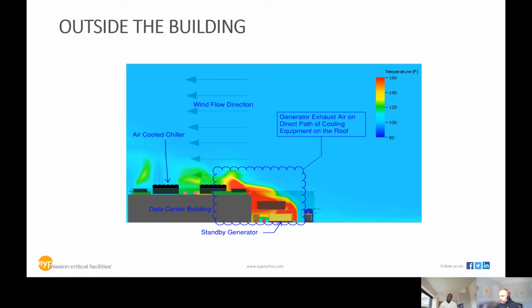If you think of each engine, the air requirement is over 150,000 cubic feet per minute. With all those engines, we were looking at 7 million cubic feet per minute of air being moved. That had a very big impact on the equipment located up on the roof - the air-cooled chillers were located up there, and they were impacted by the hot air coming out from the engines.